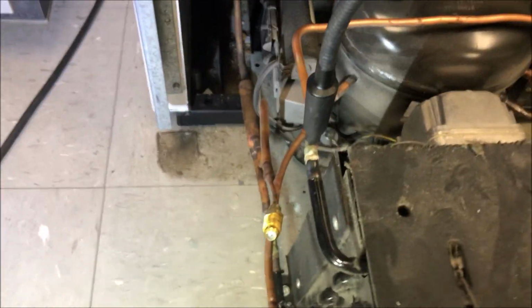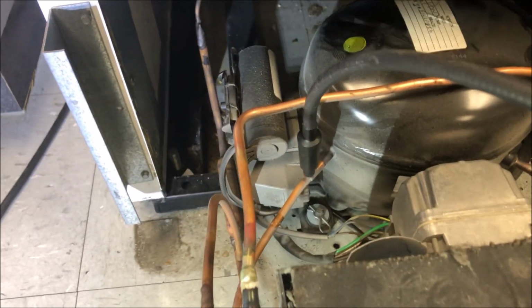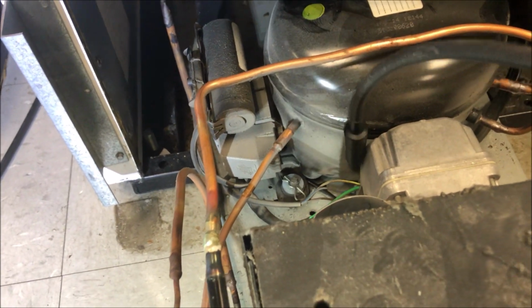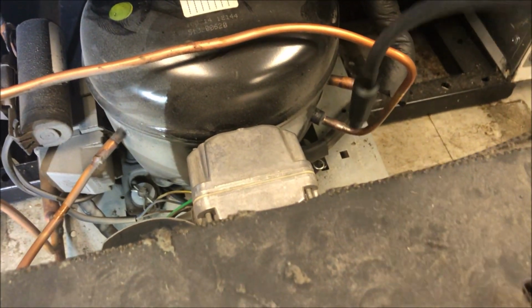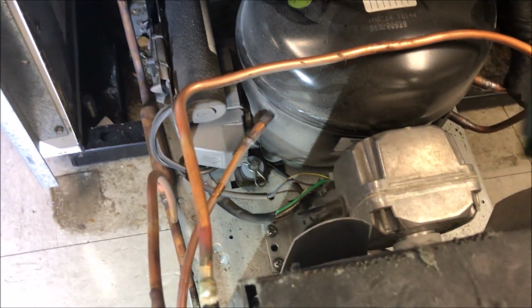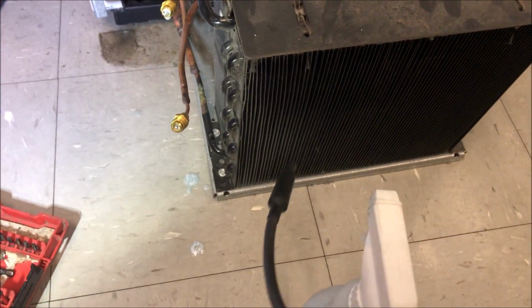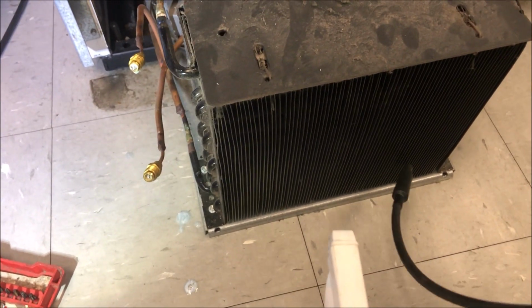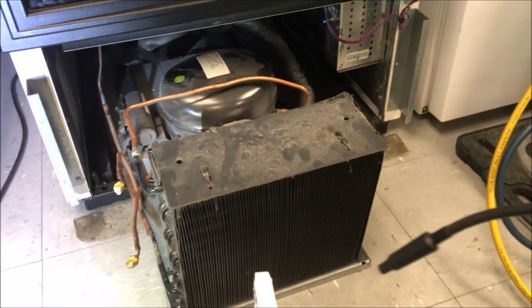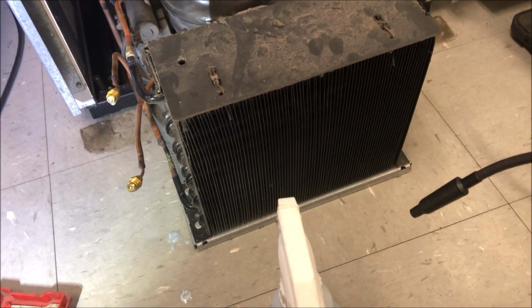And so far, so good. No leaks. Always check if another technician's been there. Always check their joints. Always check those factory ones too. We've had some leaks there on the compressors before. And then just a quick sweep of the condenser. It's rare I find a leak in the condenser. And looks like we are leak free in this condenser section. We're all good to go to give our quote now.